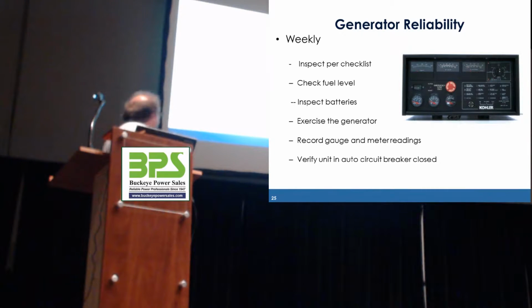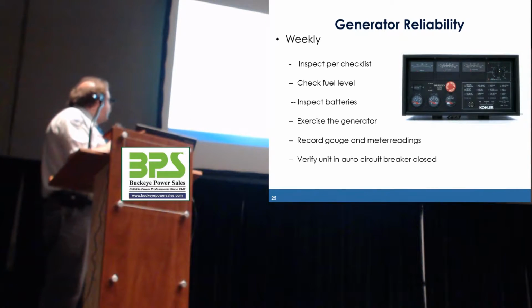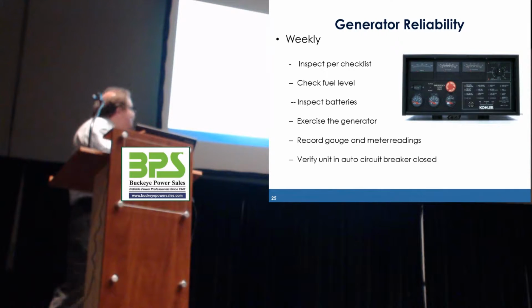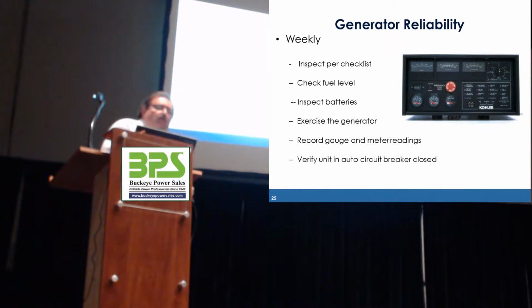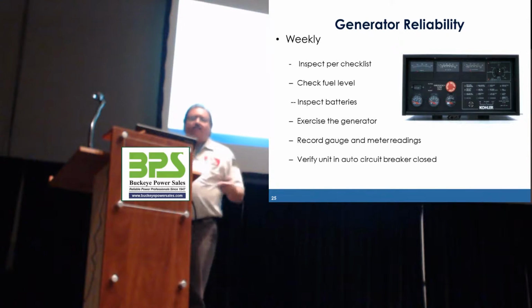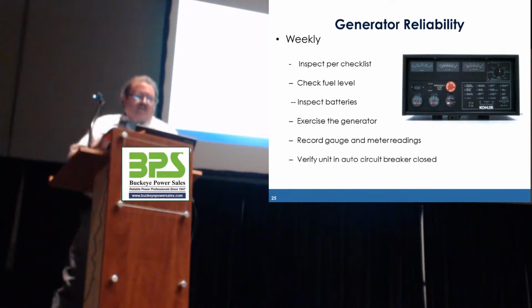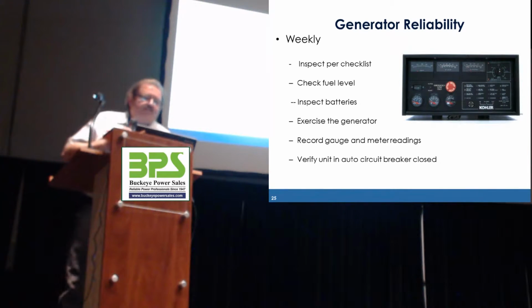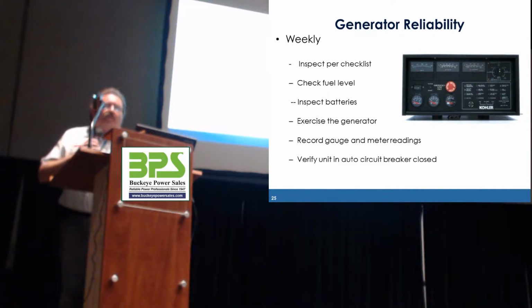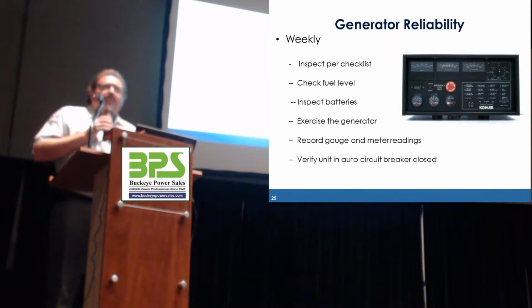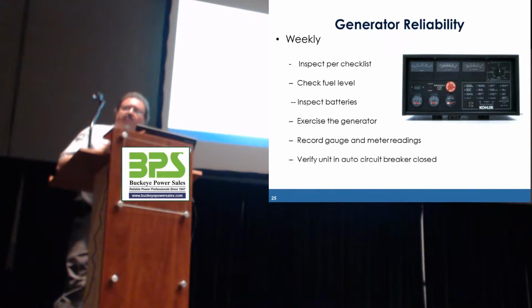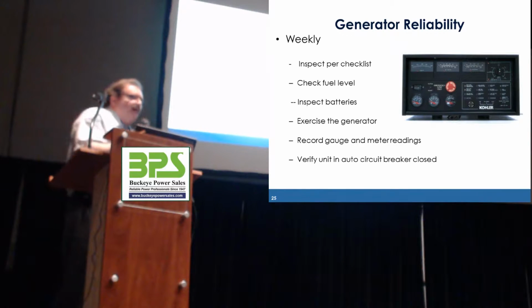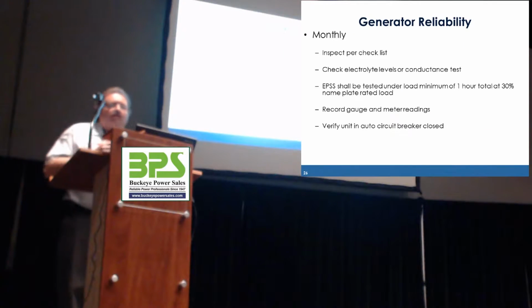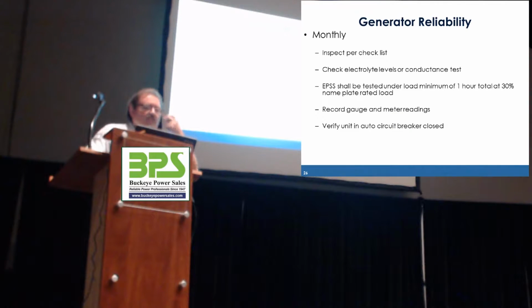So weekly, we want to do a few things. We want to make sure that we're checking the fuel level and inspecting the batteries. We want to make sure that the generator is exercising weekly, even if it's unloaded. It's our responsibility to record the gauge and meter readings, and then when you're done, make sure that everything is ready to go, that the unit's back in automatic, and that the circuit breaker is closed if you've opened it.